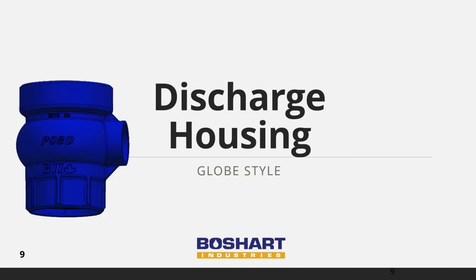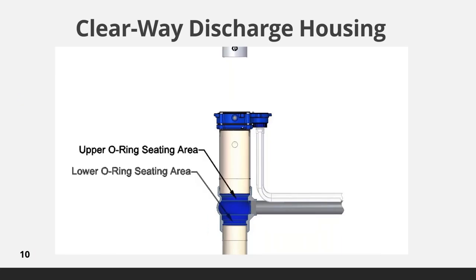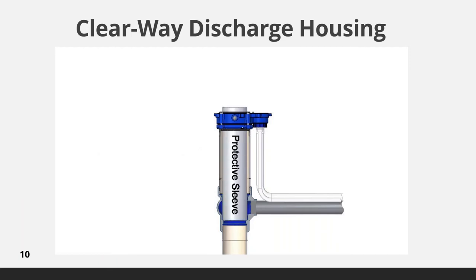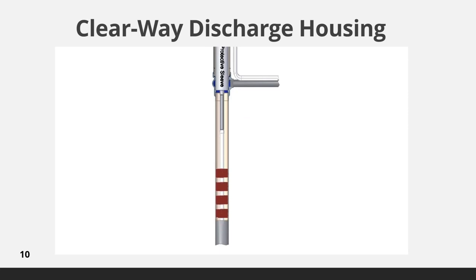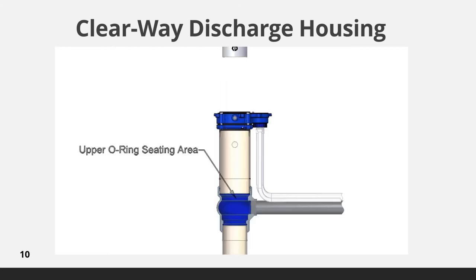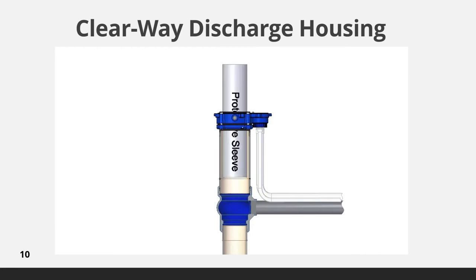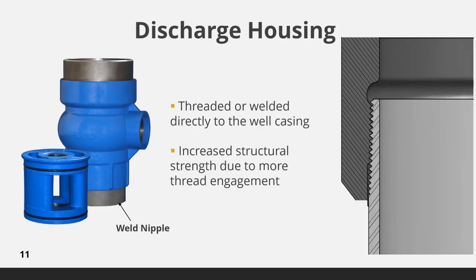We will now take a look at the discharge housings. The clearway discharge housing design has no reduction in size, providing full bore passage through the discharge housing for pump installation or well rehabilitation. This animation shows the insertion of a protective sleeve of equal size to the well diameter that protects the O-ring seats when equipment, like a brush, is lowered through the discharge housing for cleaning the casing or well screens. The threaded connections in the discharge housing are specially designed to ensure the full thread of the weld nipple and upper barrel are fully protected in the housing.